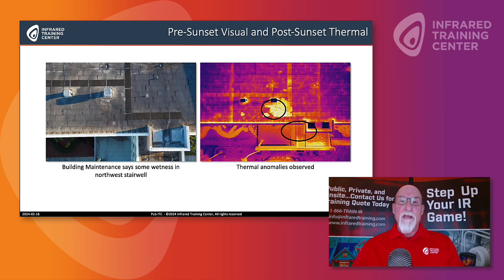The customer indicated to me that they have this leaking. They've got wetness in the stairwell, so they want me to locate where that is. So it's very crucial that I get there earlier in the day and get a good lay of the land, or should we say a good lay of the roof. It's pretty difficult when the sun has gone down to navigate around that roof, for safety reasons, and also you're just going to miss opportunities to spot potential problems before you even do the infrared scan.